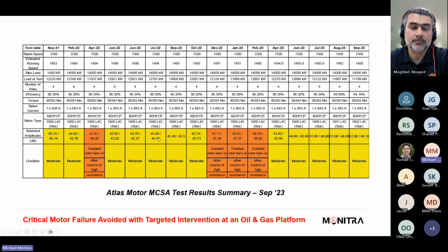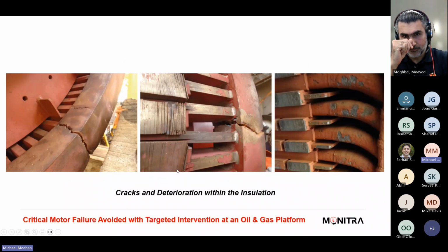We did this for an oil and gas operator out of Africa. It took some time for them to take this motor offline, but you can clearly see quite significant sideband readings. When they did take it offline, this is the end finding: the cracks are fairly significant. If that had been left in for much longer, it would have destroyed the whole motor. You can see they were starting to unlaminate, and there was activity starting to hit the end windings. It's a good case study. The client would not have taken this out of service if we hadn't identified this, so it shows the importance of doing condition monitoring.